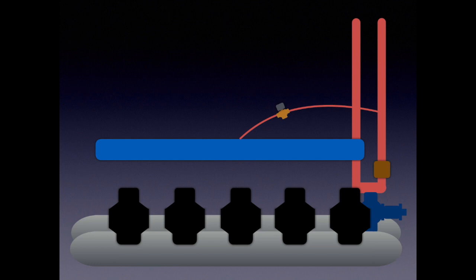These are check valves. These are my representation of check valves. These prevent refrigerant from flowing back into the unused portion of the condenser. So that we truly only have half the condenser going when we're in split condenser.